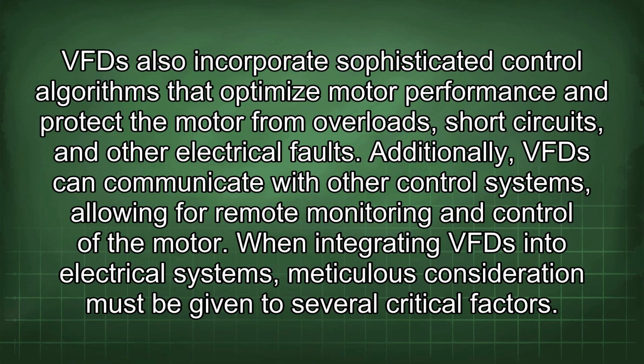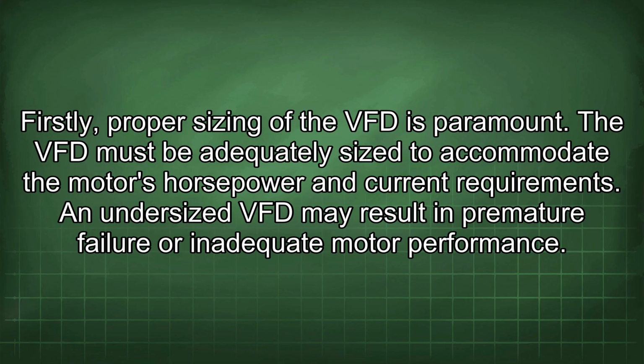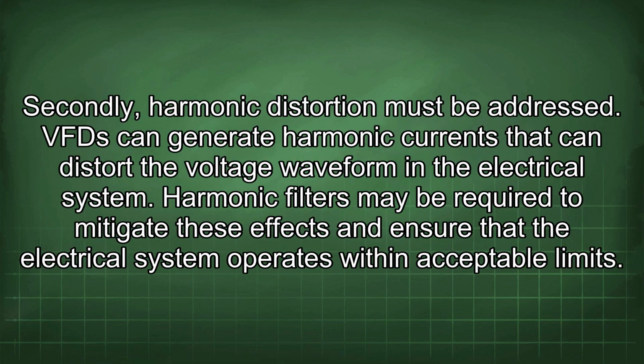When integrating VFDs into electrical systems, meticulous consideration must be given to several critical factors. Firstly, proper sizing of the VFD is paramount. The VFD must be adequately sized to accommodate the motor's horsepower and current requirement. An undersized VFD may result in premature failure or inadequate motor performance. Secondly, harmonic distortion must be addressed. The VFD can generate harmonic currents that can distort the voltage waveform in the electrical system. Harmonic filters may be required to mitigate these effects and ensure that the electrical system operates within acceptable limits.